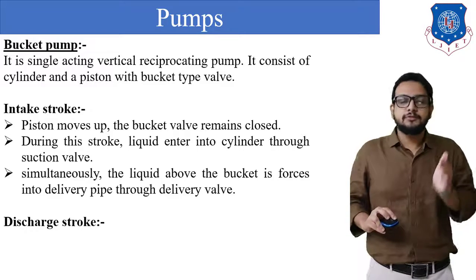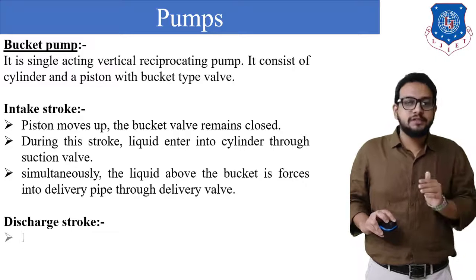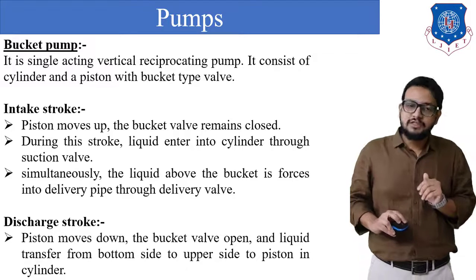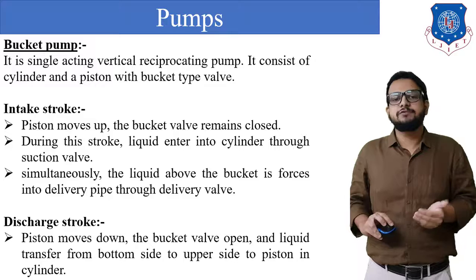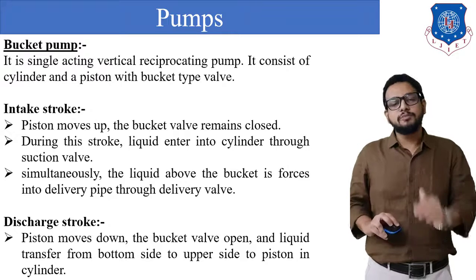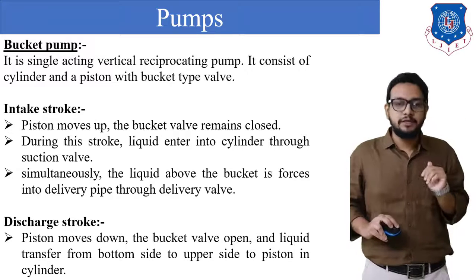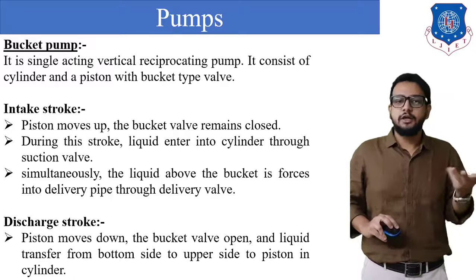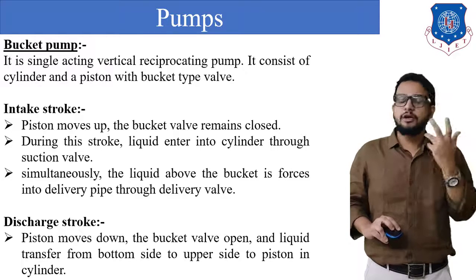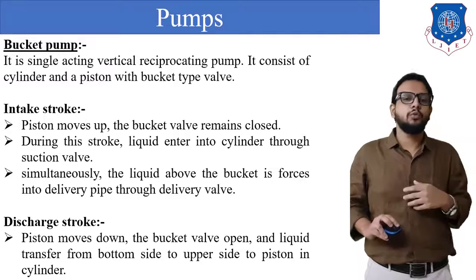Discharge stroke, which means a downward stroke, is this. The piston moves in a downward direction, the bucket valve opens, and liquid is transferred from the bottom side of the piston to the top side of the piston in the cylinder. So the working is very simple. You just need to explain two strokes, that is, the upward stroke and the downward stroke.